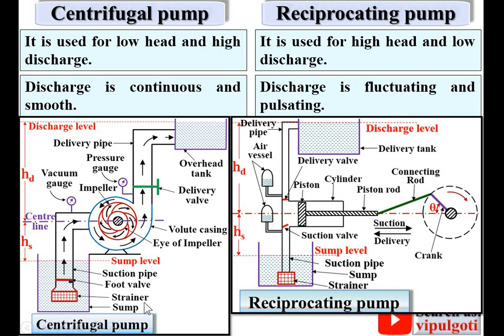Looking at the figures of centrifugal pump and reciprocating pump: in the centrifugal pump, the impeller rotates continuously, so the flow is continuously flowing and you get a continuous discharge. Whereas in the reciprocating pump, first suction occurs and then discharge, giving pulsating flow. The piston has accelerating and decelerating motion, which causes the fluctuating discharge.